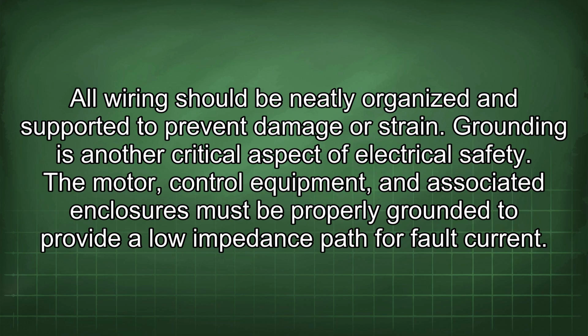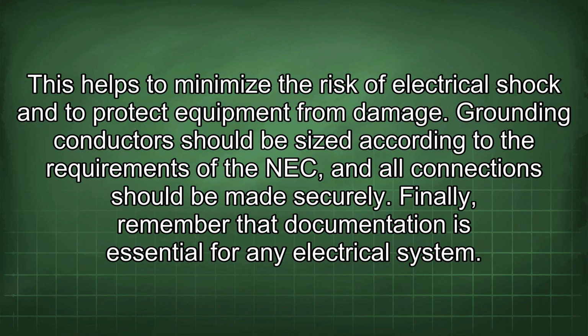Grounding is another critical aspect of electrical safety. The motor control equipment and associated enclosures must be properly grounded to provide a low impedance path for fault current. This helps to minimize the risk of electrical shock and to protect equipment from damage. Grounding conductors should be sized according to the requirements of the NEC, and all connections should be made securely.